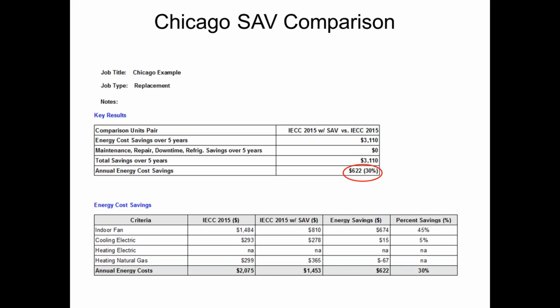Now, just so you guys are aware, we typically don't make 2-speed motors anymore because that's fairly costly to have double windings. So pretty much you're going to get a VFD that's programmed to only run at 2 speeds. That's how we're doing the 2-speed control. But if you remember, going from an entry-level unit to a code-compliant unit only saved me 1% energy. So instead of doing that, if I make my entry-level unit code-compliant by putting a staged air fan on like this, I'm going to get a lot of real savings to go along with my code compliancy.